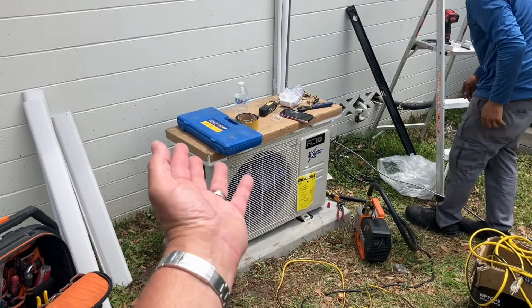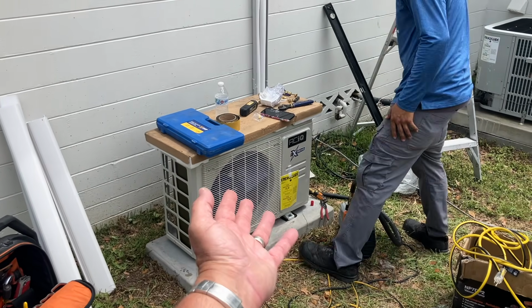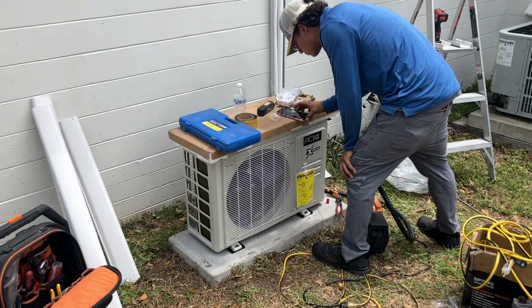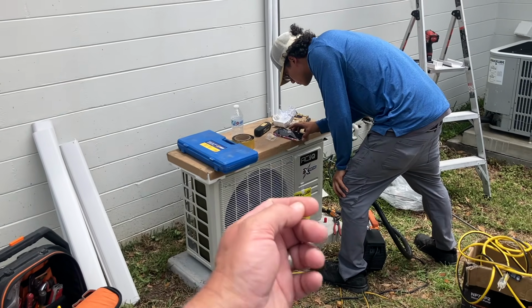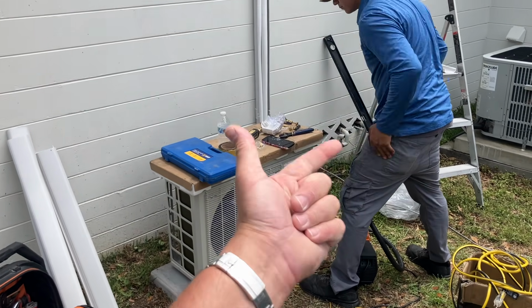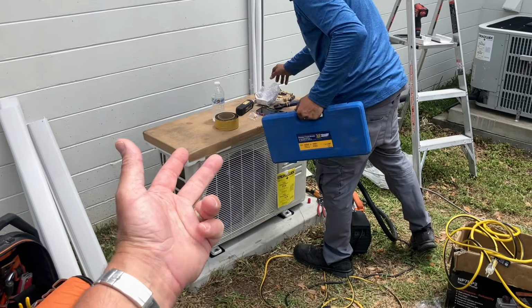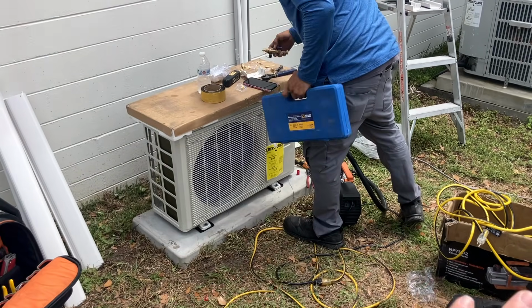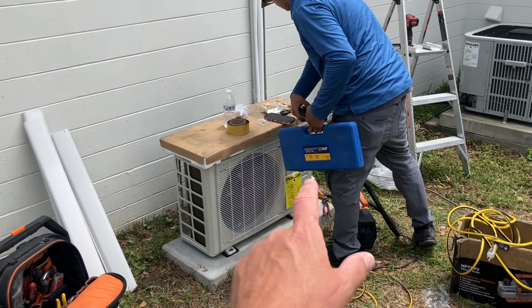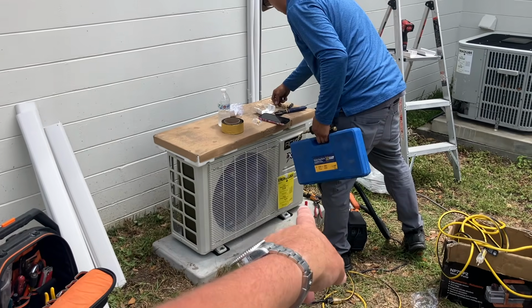And it gives the fellas an opportunity to finish up the install by doing the electric. As long as we keep pulling down a vacuum, we can run our disconnect, our whip, our surge protection device, start cleaning up, and leave this vacuum pump on for as long as possible. Let this be the last thing you take off and bring back to the truck.